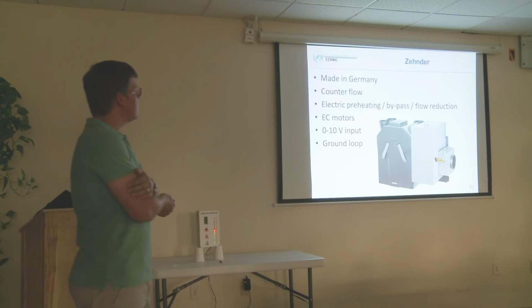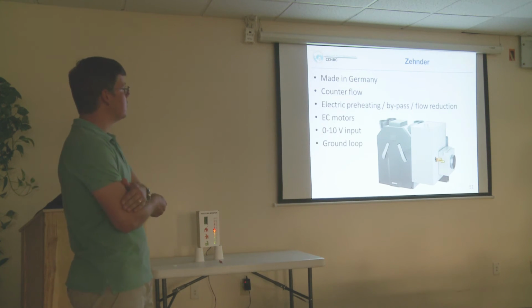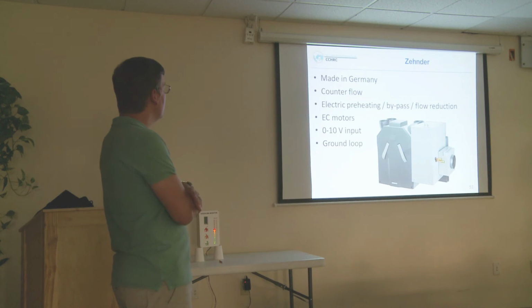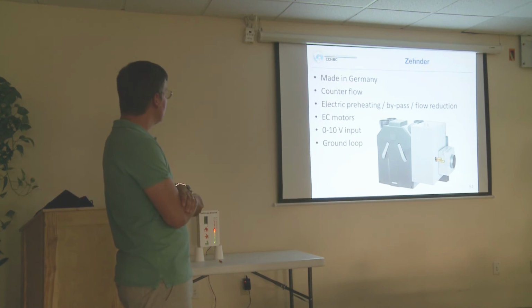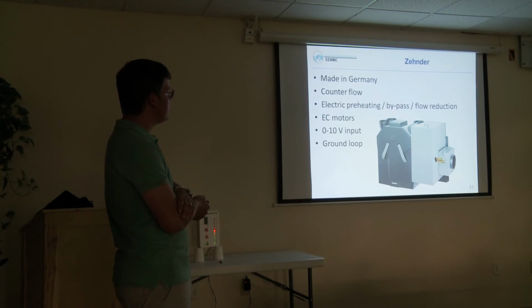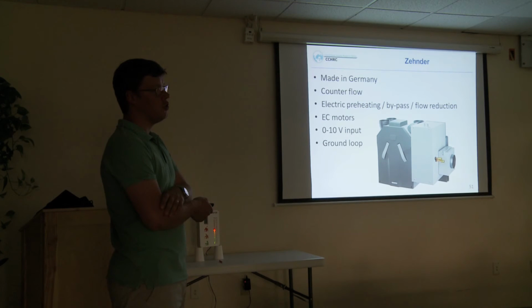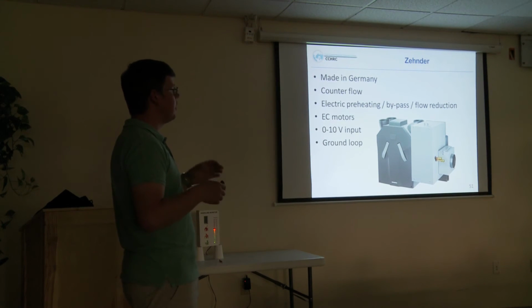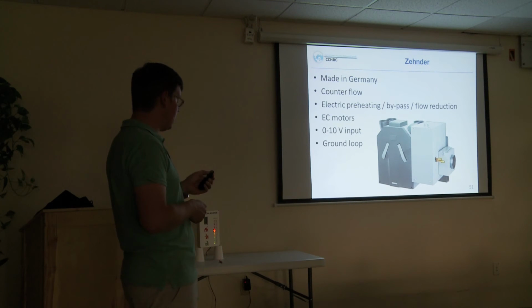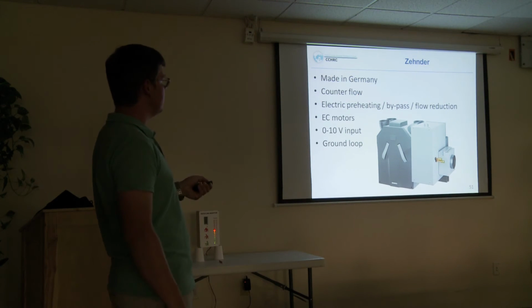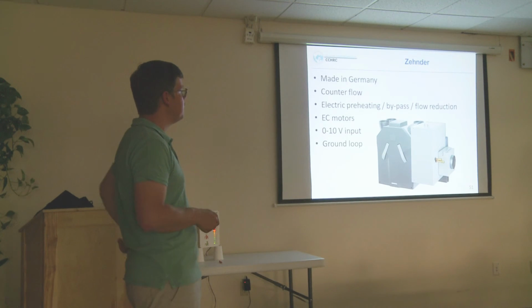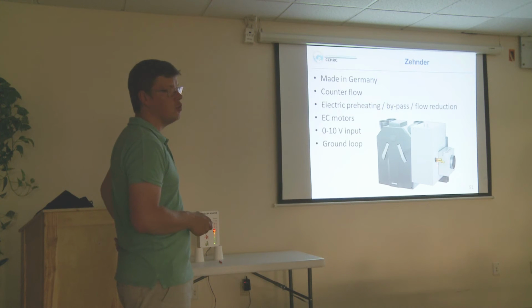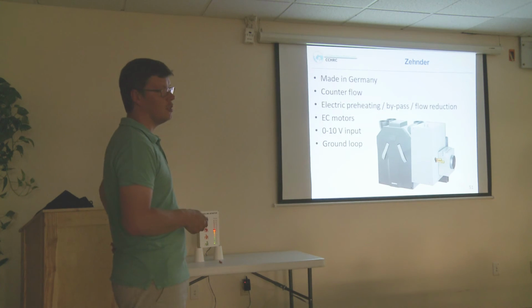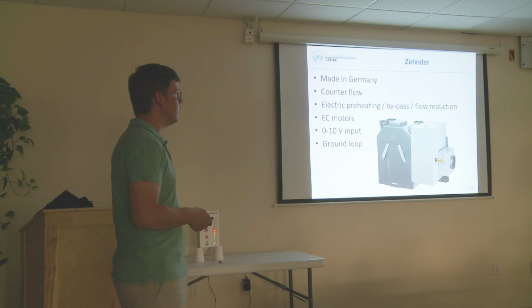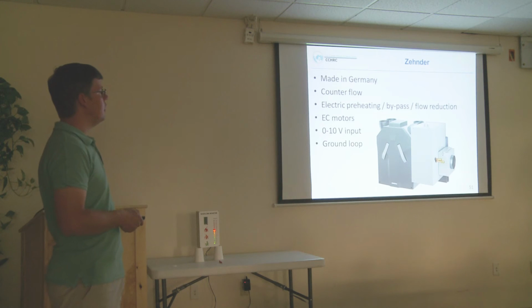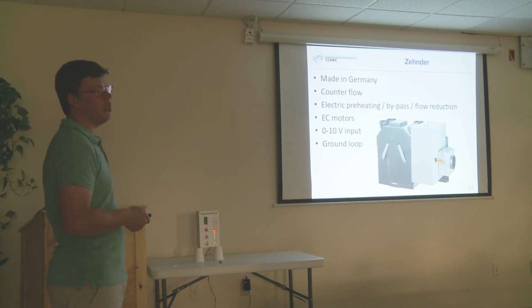There comes the German unit, Zehnder, that also has been used here a couple of times, at least I have seen. It has a counterflow heat exchanger. It has electric preheating. It also has a bypass, and it also has a flow reduction. So when you install it, you can give priority to different strategies, and you can decide, to some degree, what strategy it will use. It has a fitted preheating coil, which can be hooked up to a ground loop or to any other hot water source. So if you have a boiler which heats water, you can hook it up to that. Instead of electric preheating, you can just preheat with hot water.